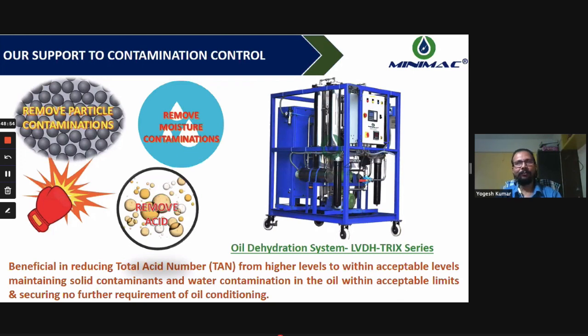LVDH-TRIX. This name looks very tricky, but it is actually an abbreviation: TAN reduction by ion exchange. TAN is total acid number. While we are talking about the control fluid or EH oil fluid or phosphate ester fluid, sometimes we call it P fluid or FRF. There are many names, but all are just used for the turbine governing system, in the PSU as well as Chinese, Japanese, Korean, whichever manufacturers of the equipment, especially turbines, use it.